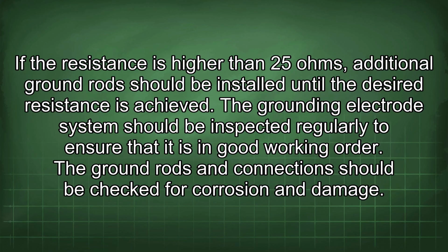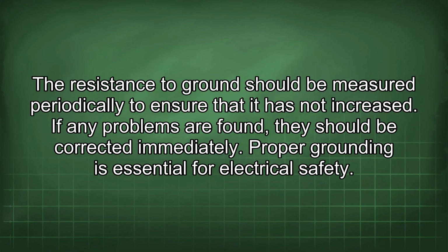The grounding electrode system should be inspected regularly to ensure that it is in good working order. The ground rods and connections should be checked for corrosion and damage. The resistance to ground should be measured periodically to ensure that it has not increased. If any problems are found, they should be corrected immediately.